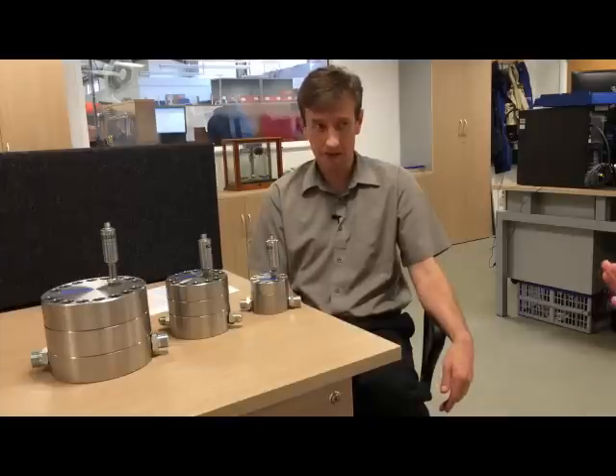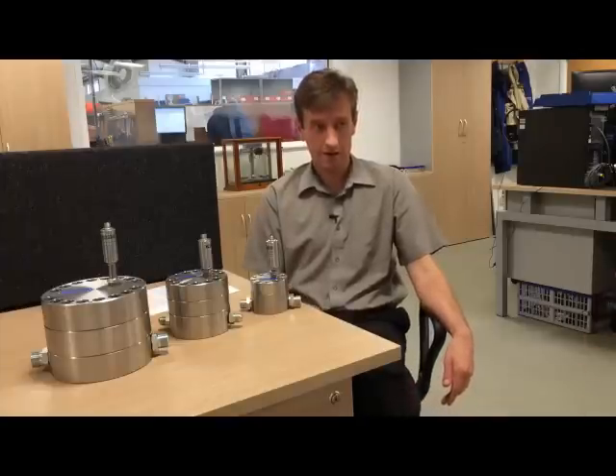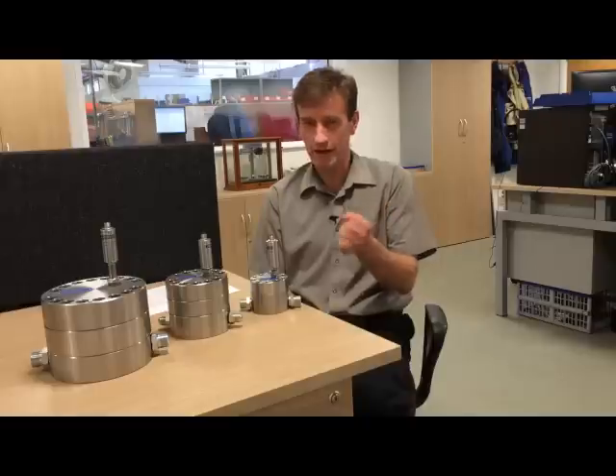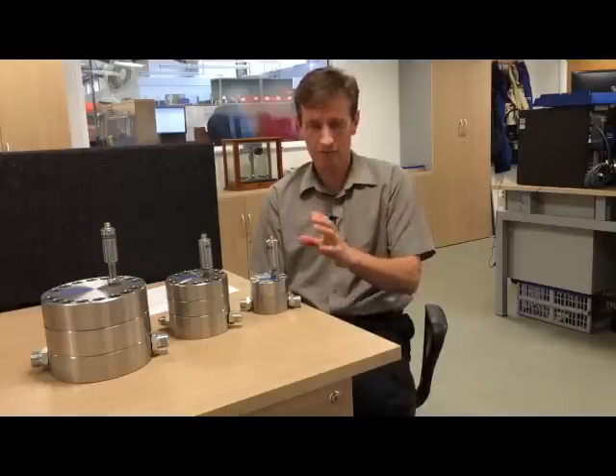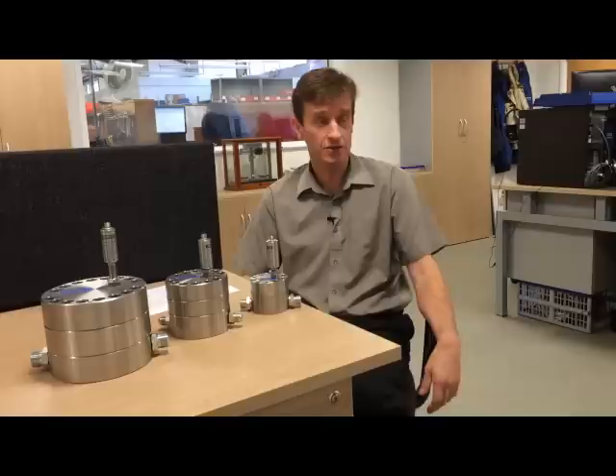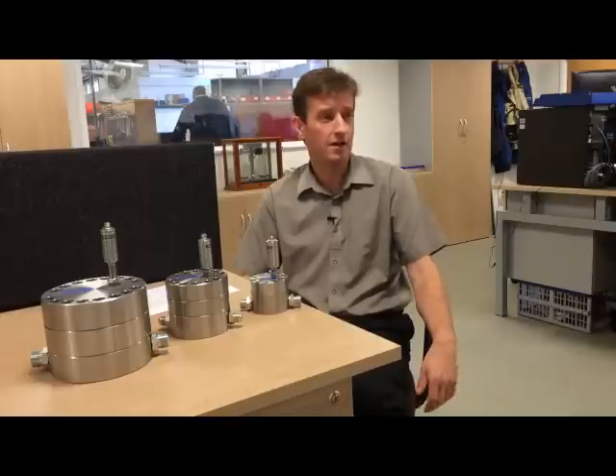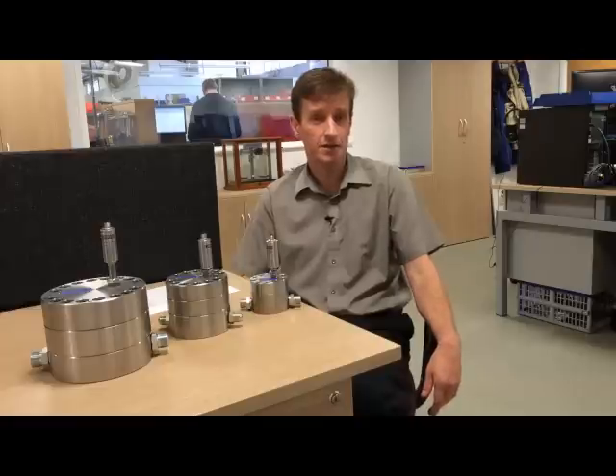The customer doesn't have to do anything. They just take that signal. Well, that's the advantage of having a microprocessor linearization built into the transducer. All the calibration points are programmed into the transducer. The customer then just connects it up to their device, handheld unit, PLC unit, just puts in a zero point and a full-scale point for flow relative to the output type. And that's it. It's linearized between those two points.